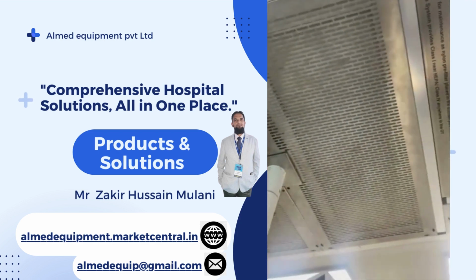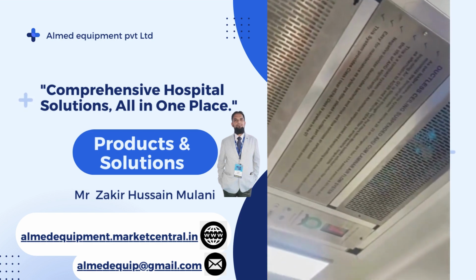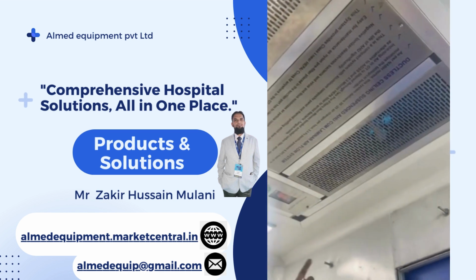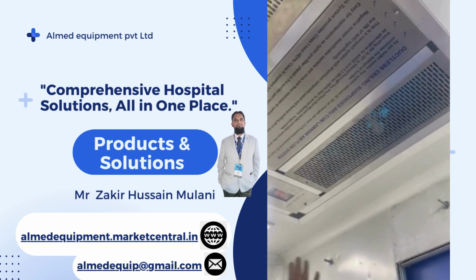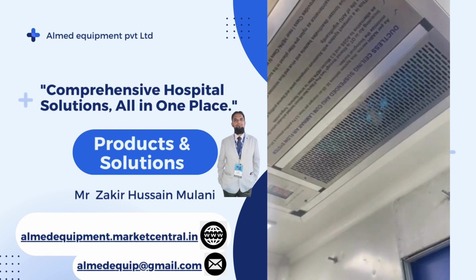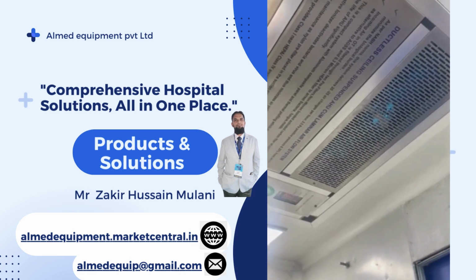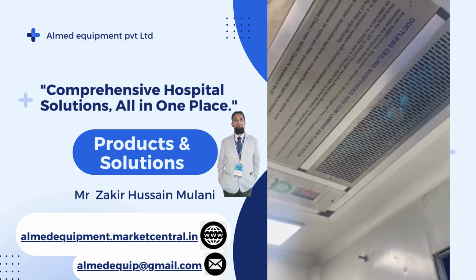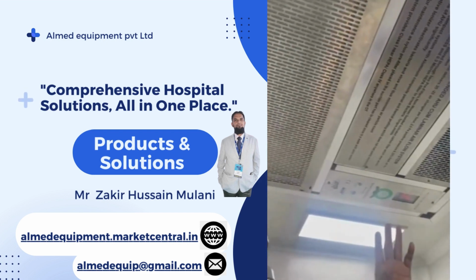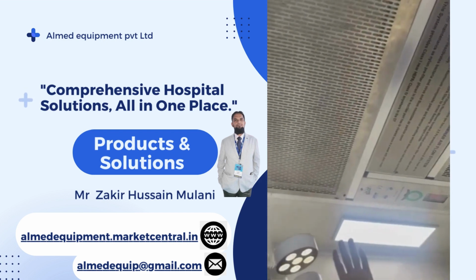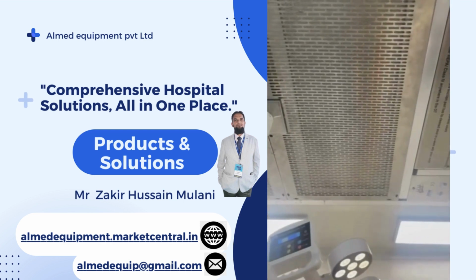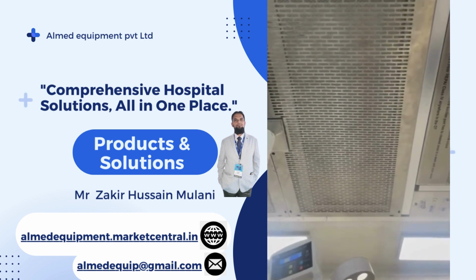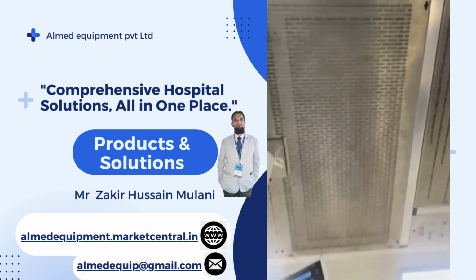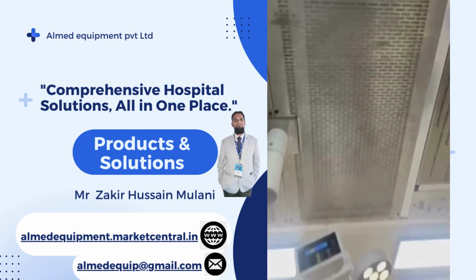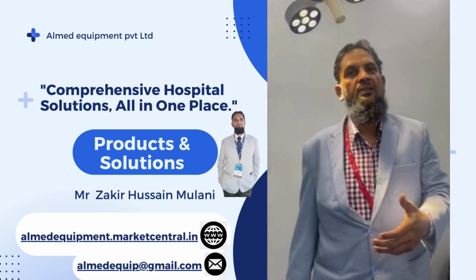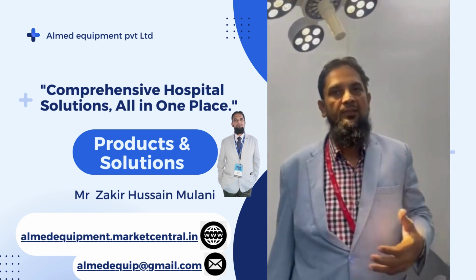The air gets sucked in from this place, with 20% fresh air also coming into this chamber, and both mix together. This is the first air treatment chamber, where we have given negative ionizers and UV lights. After that, we have given the cooling coil in between, and from this the air passes through the HEPA filter onto the table level. Before the HEPA we have given an activated carbon filter also, which minimizes other gases like CO2 or anesthesia gases. So you will find a lot of freshness.